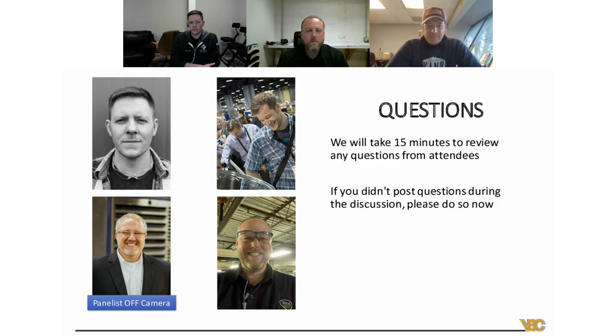We've had issues with, again this is when we were overworking the chiller a bit, high discharge pressures where we had to hose down the condensing coils with water to try to get them cooled. If you're cooped up inside a building with no real airflow and no options for that kind of stuff, you're taking that already delicate balance further. If your manufacturer is building the system for your hot climate outside, you're probably going to be just fine. But it's a delicate balance, and I think you're inviting a lot of different issues and the inability to run quick and dirty solutions in a pinch if you're inside a building there.